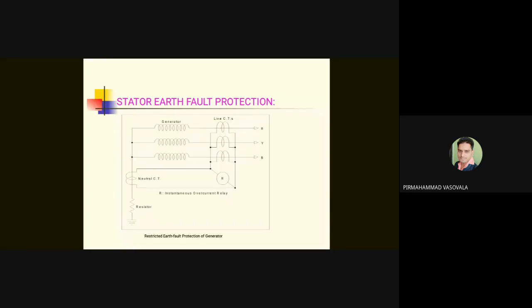unprotected. For a large 210 megawatt generator, where we reduce the value of the earth fault current to 2 ampere, 100% of the winding is not protected. If you connect like this, it means only a single percentage of the winding can be protected by stator earth fault protection. So just to tell you, this is a useless circuit. This is not what is used.